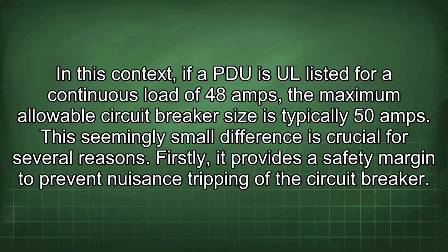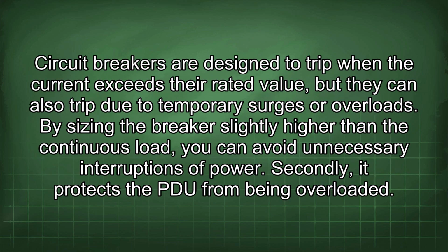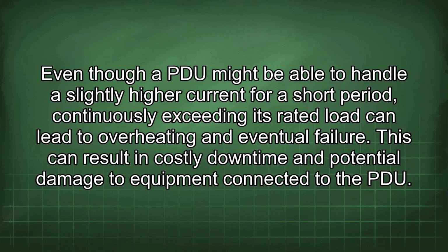Firstly, it provides a safety margin to prevent nuisance tripping of the circuit breaker. Circuit breakers are designed to trip when the current exceeds their rated value, but they can also trip due to temporary surges or overloads. By sizing the breaker slightly higher than the continuous load, you can avoid unnecessary interruptions of power. Secondly, it protects the PDU from being overloaded. Even though a PDU might be able to handle a slightly higher current for a short period, continuously exceeding its rated load can lead to overheating and eventual failure. This can result in costly downtime and potential damage to equipment connected to the PDU.